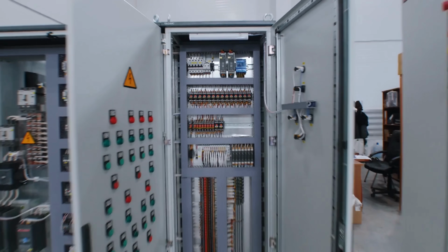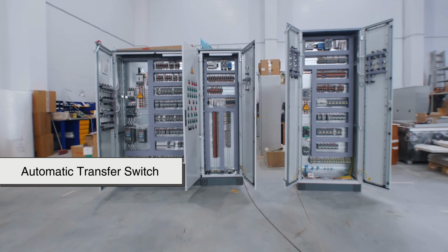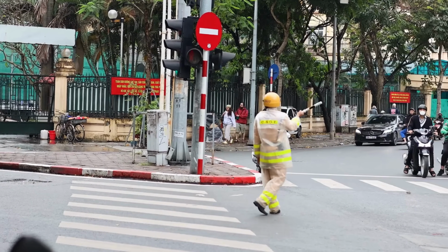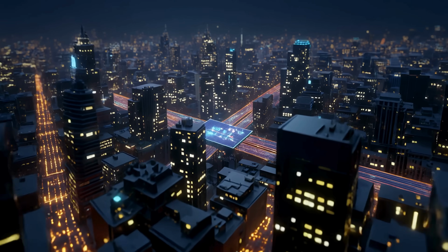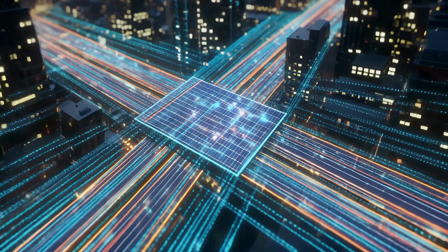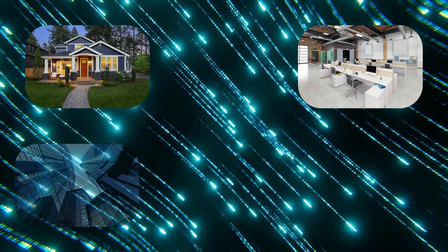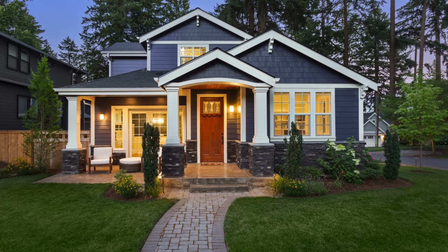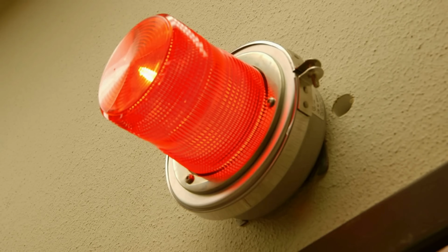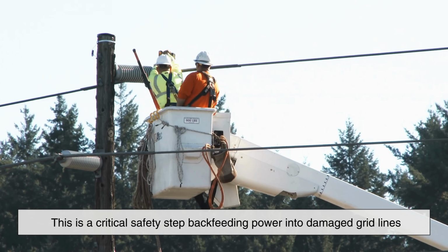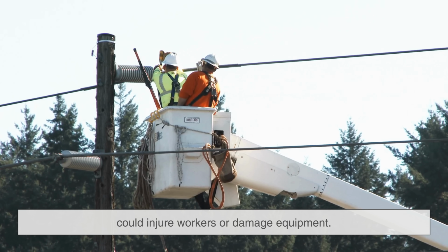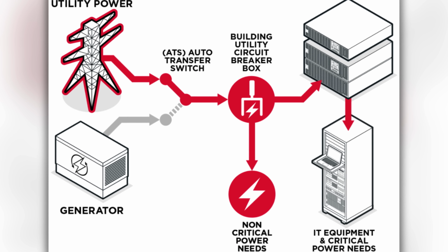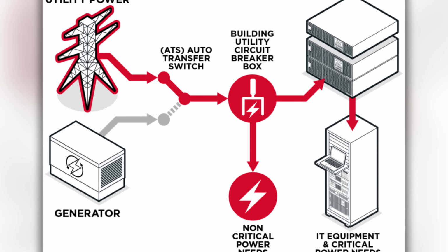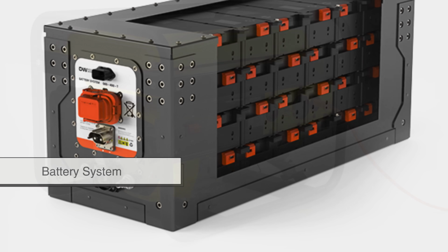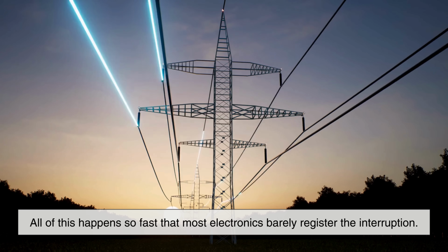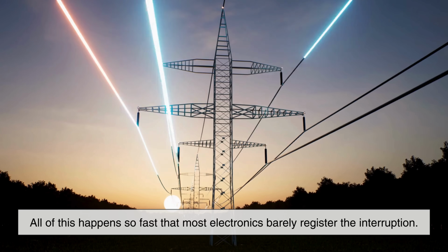At the heart of most instant backup systems is a device called an automatic transfer switch, or ATS. Think of it as a highly disciplined traffic officer for electricity. Under normal conditions, it allows power from the main utility grid to flow into your home, office, or building. But the moment it senses that utility power has failed or become unstable, it immediately disconnects from the grid. This is a critical safety step — backfeeding power into damaged grid lines could injure workers or damage equipment. Once the grid is isolated, the transfer switch connects your electrical system to a backup source, such as a generator, battery system, or inverter. All of this happens so fast that most electronics barely register the interruption.